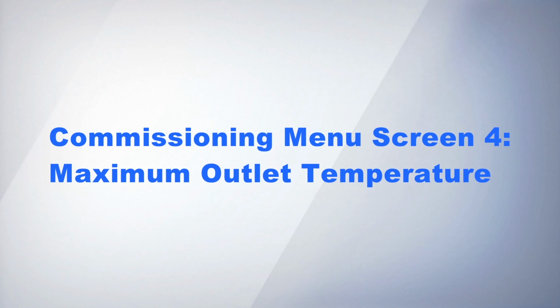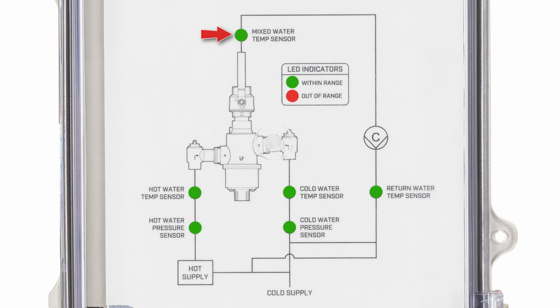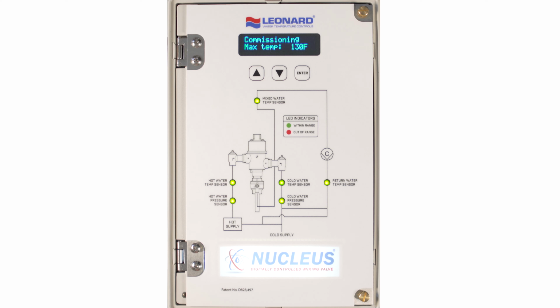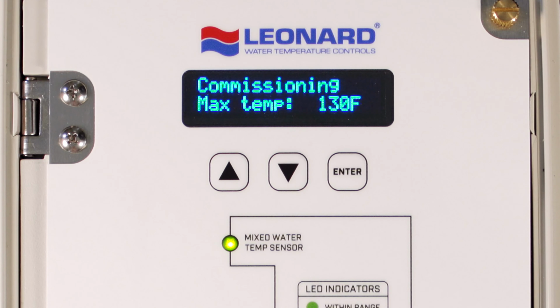Commissioning menu screen 4, maximum outlet temperature. Pressing down 3 times displays max temp. This is maximum alarm temperature as measured on the primary outlet temperature sensor of the Nucleus mixing valve RTD T3. Measured values above this value will cause an alarm condition that will switch a relay to normally opened. See O&M manual for the alarm relay details. Default value is 130 degrees Fahrenheit.